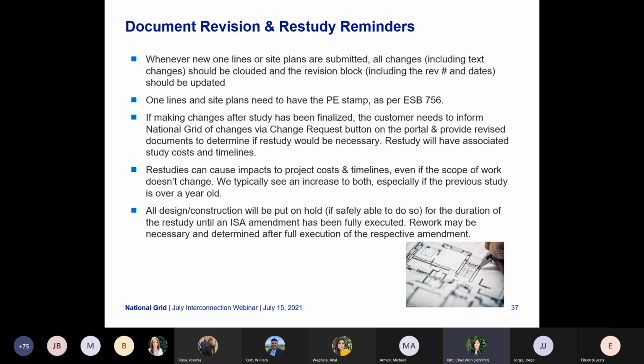And then all the one lines and site plans do need to have a PE stamp, and this is per our ESB standards. If you're making changes after a study has been finalized, the customer does need to inform National Grid of the changes via the change request button on the portal, as well as provide the revised documents to determine if a restudy would be necessary. And if we do determine that a restudy is necessary, there would be associated costs and timelines that we would inform you of.